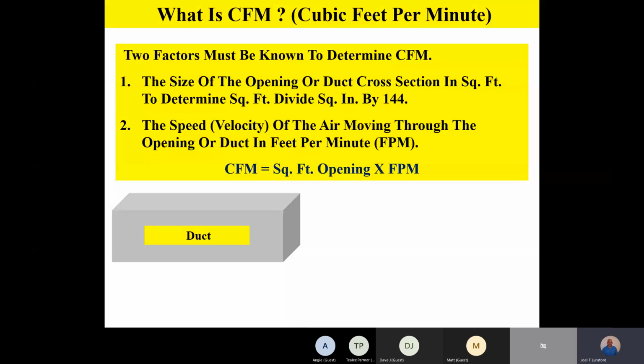And we find that the actual square foot cross section of that 16-inch duct is 1.40 square feet. Any questions or comments on how we derived that number? We'll do a couple more examples, but we want to make sure everybody knows how we got there first. Everybody good?